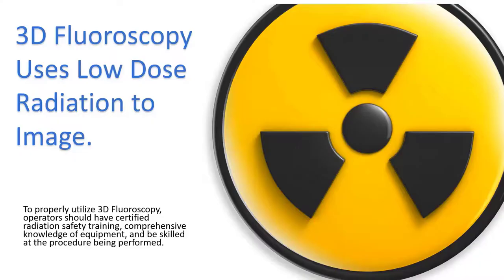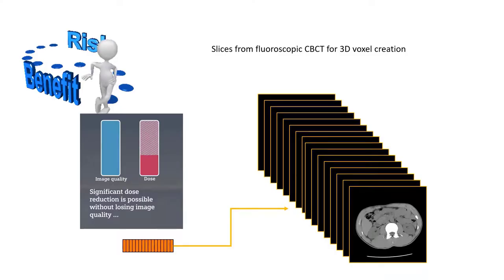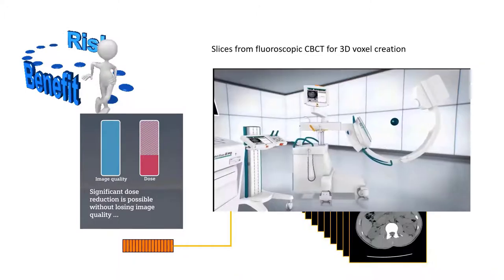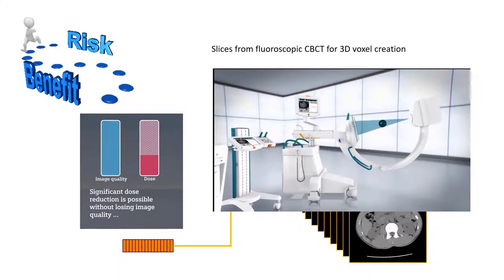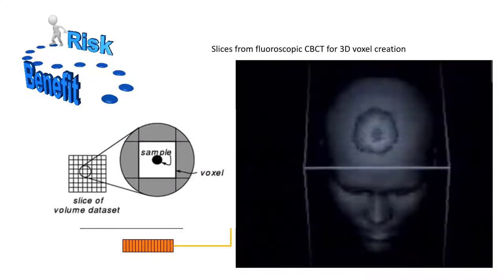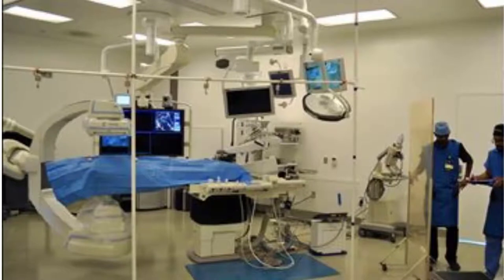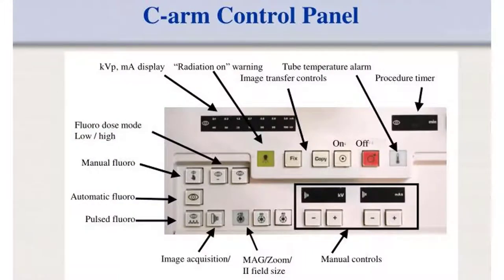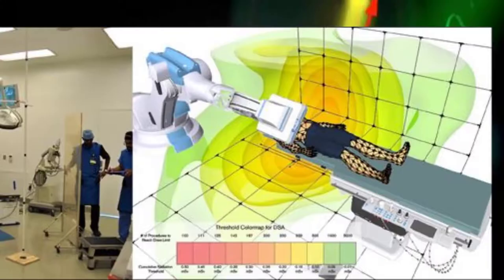To properly utilize 3D fluoroscopy, operators should have certified radiation safety training, comprehensive knowledge of the equipment they are using, and be skilled at the procedure being performed. Using cone beam CT for 3D fluoroscopy, we create image slices that are stacked to create a voxel — a solid block of data or image. The operator selects the time of exposure, the amount of ionizing radiation (milliamperage or mA), and the KVP (kilovolts peak) used to penetrate the tissue. These factors are called exposure technique.